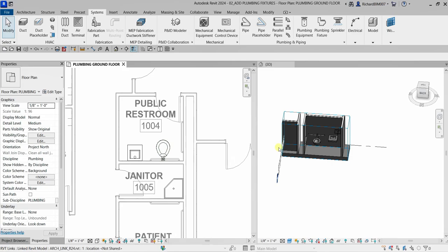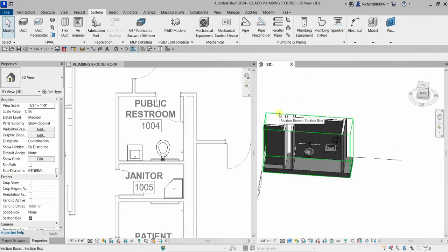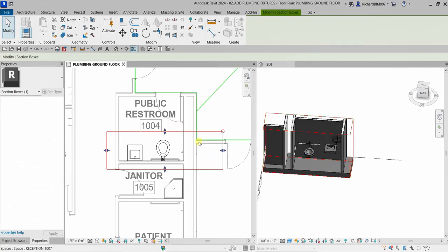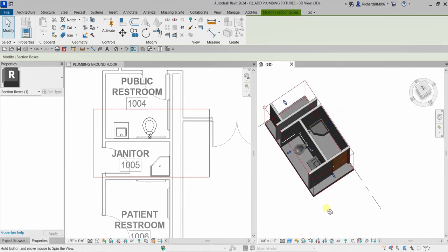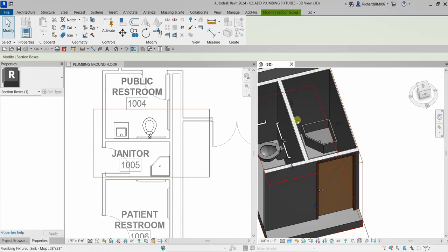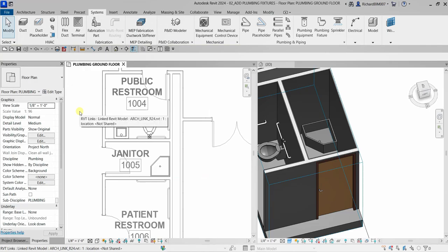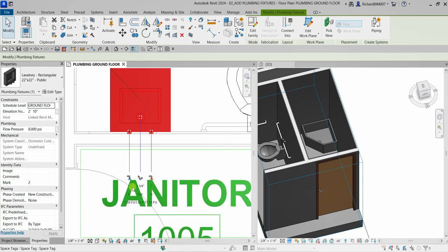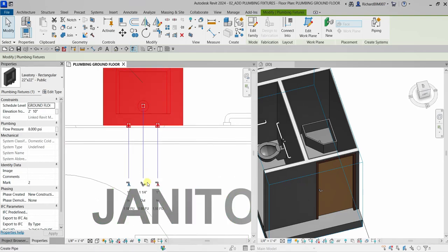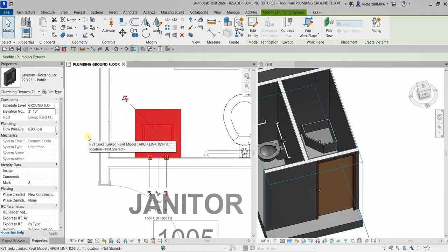Zoom out a bit, then in the 3D view click the Section Box to pan and adjust the view so you can see the mop sink. When you select a Revit MEP family — for example the lavatory — pay attention to the connector labels. These indicate the connectors placed on the fixture and report connector information: you'll see connectors for sanitary or drainage, domestic cold water, and domestic hot water.